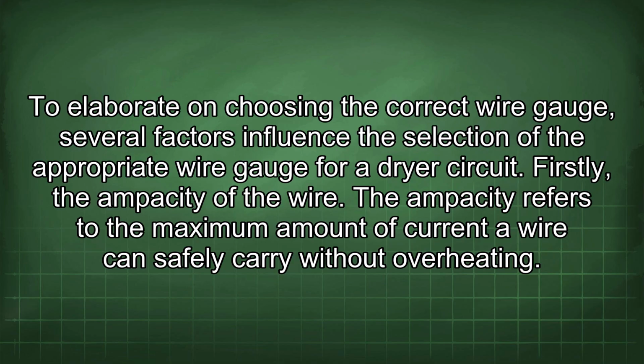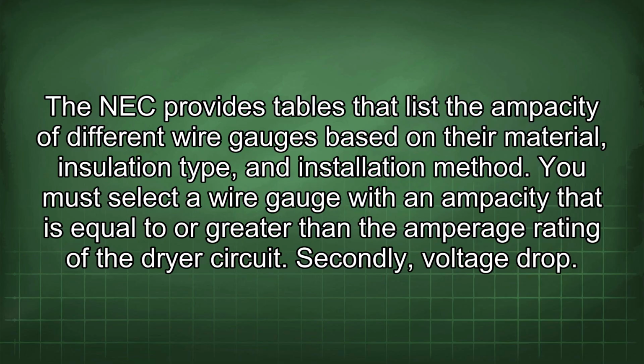To elaborate on choosing the correct wire gauge, several factors influence the selection of the appropriate wire gauge for a dryer circuit. Firstly, the ampacity of the wire. The ampacity refers to the maximum amount of current a wire can safely carry without overheating. The NEC provides tables that list the ampacity of different wire gauges based on their material, insulation type, and installation method. You must select a wire gauge with an ampacity that is equal to or greater than the amperage rating of the dryer circuit.